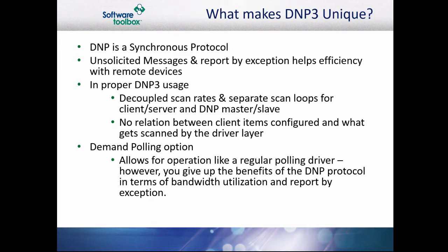There are many aspects of DNP3 that make it unique from other protocols. DNP3 is by nature a synchronous protocol. It uses both unsolicited messages and report-by-exception communications to increase efficiency in bandwidth utilization. When used properly, DNP3 decouples the scan rates between the client/server and the master/slave, meaning there is no relation between your client items that are configured and what gets scanned by the driver. That being said, DNP3 also supports the demand polling option to allow it to operate like most other drivers.